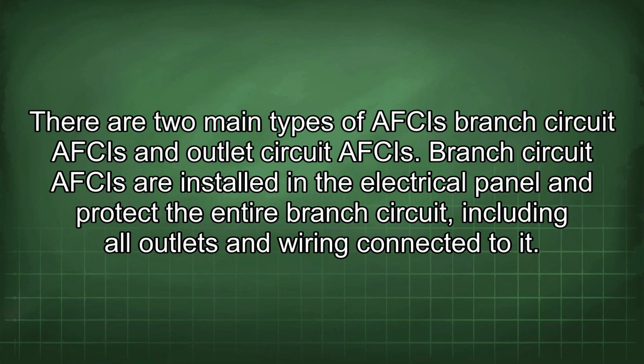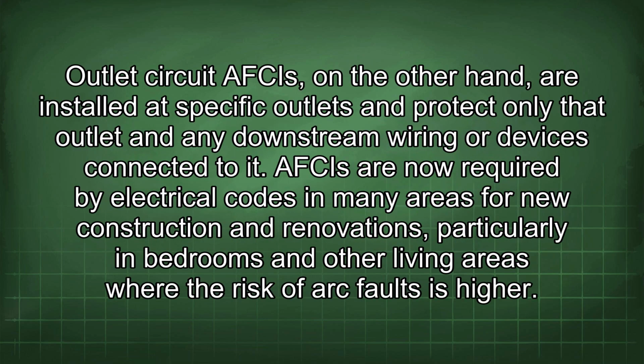There are two main types of AFCIs: branch circuit AFCIs and outlet circuit AFCIs. Branch circuit AFCIs are installed in the electrical panel and protect the entire branch circuit, including all outlets and wiring connected to it. Outlet circuit AFCIs, on the other hand, are installed at specific outlets and protect only that outlet and any downstream wiring or devices connected to it. AFCIs are now required by electrical codes in many areas for new construction and renovations, particularly in bedrooms and other living areas where the risk of arc faults is higher.